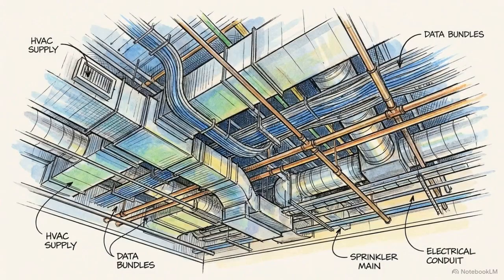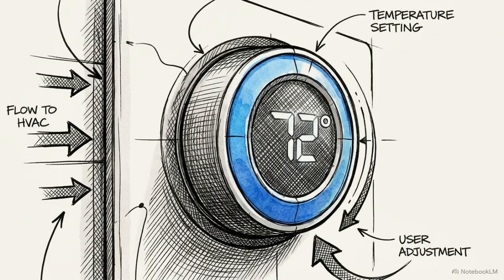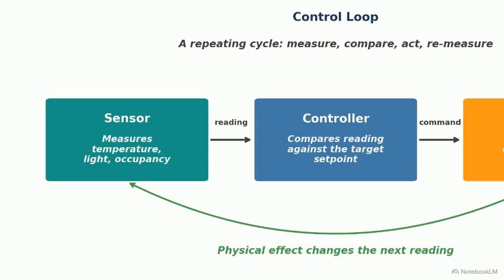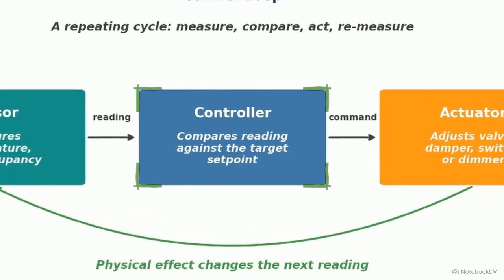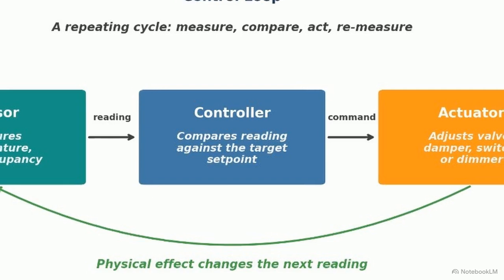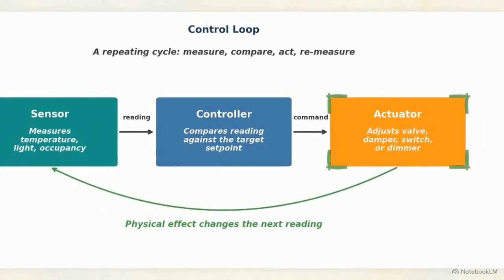So how do thousands of isolated components know exactly what to do without a human pressing any buttons? It all comes down to the control loop. This diagram shows the measure, compare, act cycle. A sensor measures a physical state. The reading goes to the controller, which compares it against the set point. If it misses, the controller commands the actuator to adjust a valve, changing the environment and feeding into the next reading.